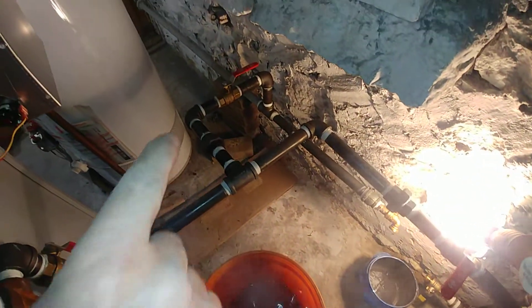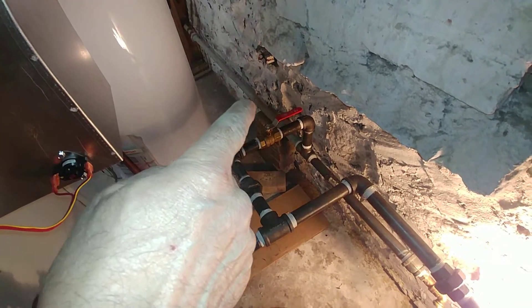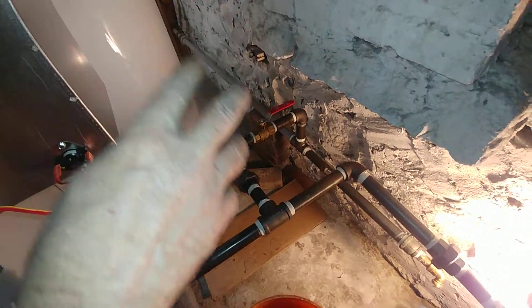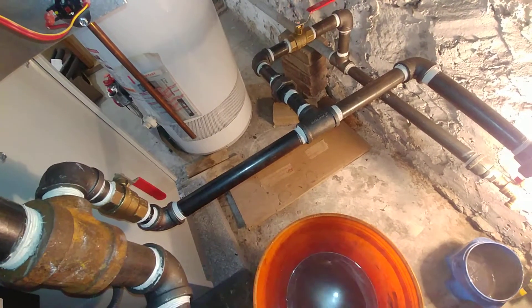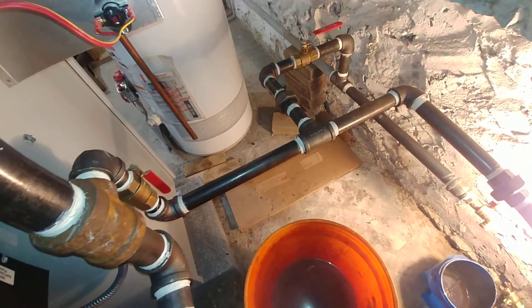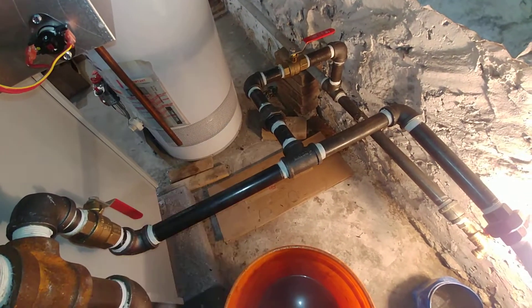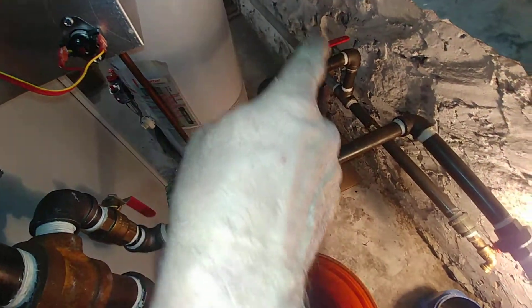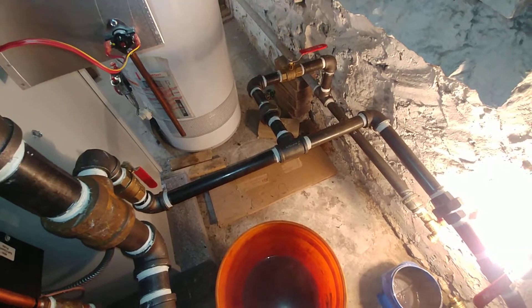You can sort of smell the oils. This valve here is open, allowing the water to return from this side of the house and get back to the boiler, and of course there's the isolation valve. When I first started this up, that union started leaking, so we were able to isolate all the valves, work on that union, and get it tight.